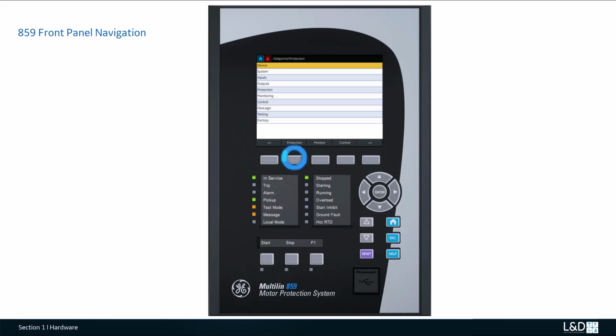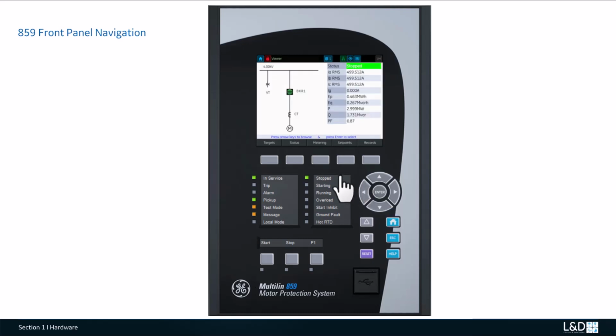We come to the protection, and from here you can see all the protection elements. Okay, so that's for the set points. We can check all the set points of the relay. Compared with the 369, there are only two main menu branches in the 369's actual values: one is the combined status and metering, and the other is the set points.